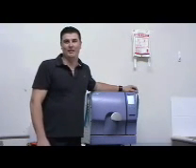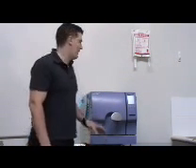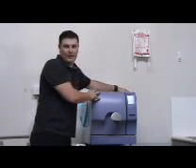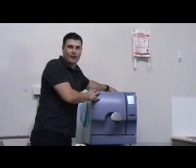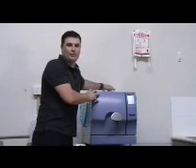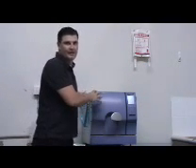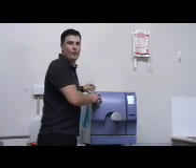Hello and welcome to your Cominox instructional DVD. By now you should have had your unit on the bench, ensuring that it is on a sturdy bench with adequate air flow behind and around the unit. By having insufficient air flow around your steriliser you could introduce problems later on, so please be sure when setting your steriliser on the bench you do allow for adequate air flow in, around, behind, and at the front.